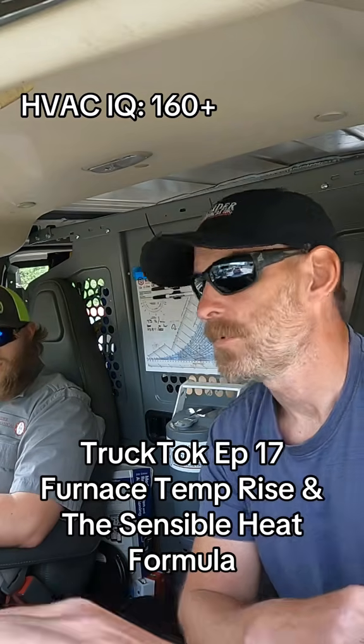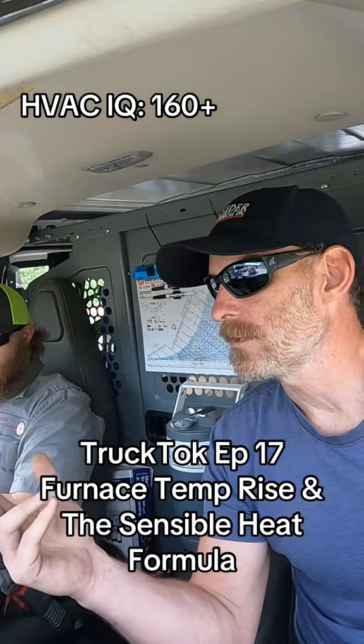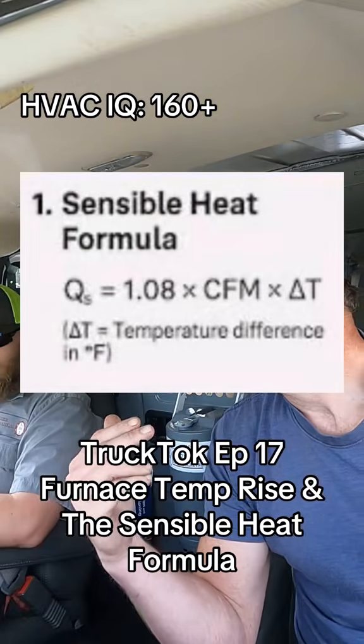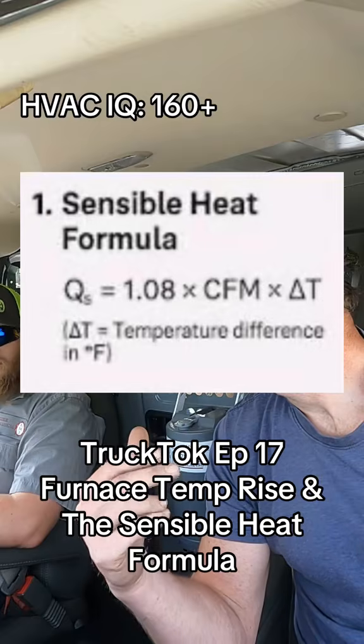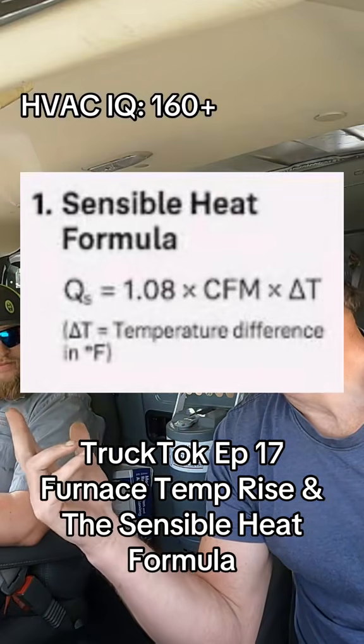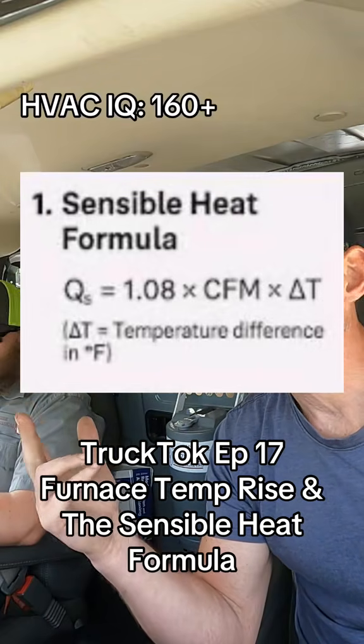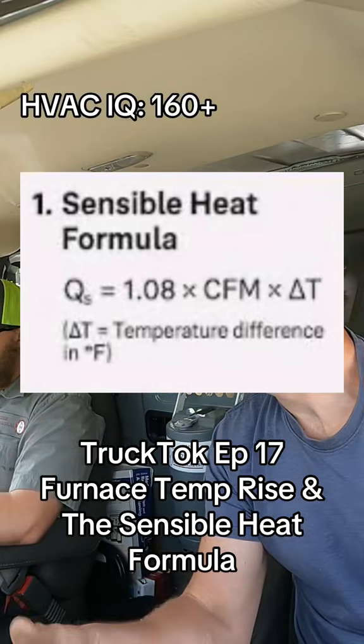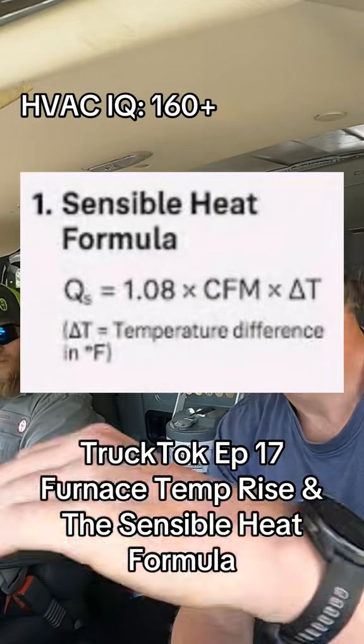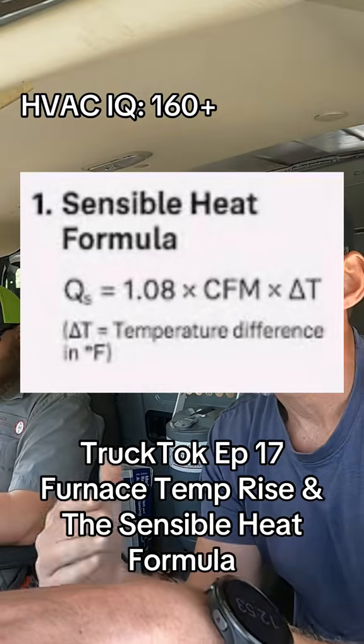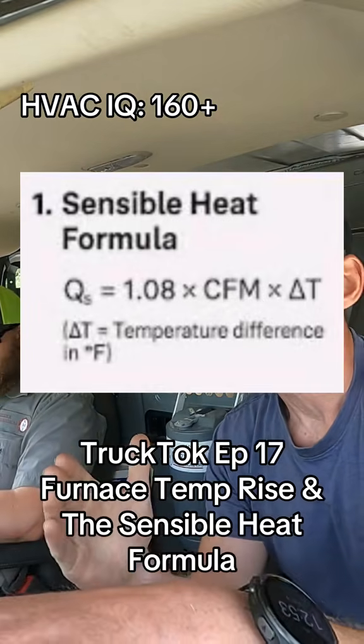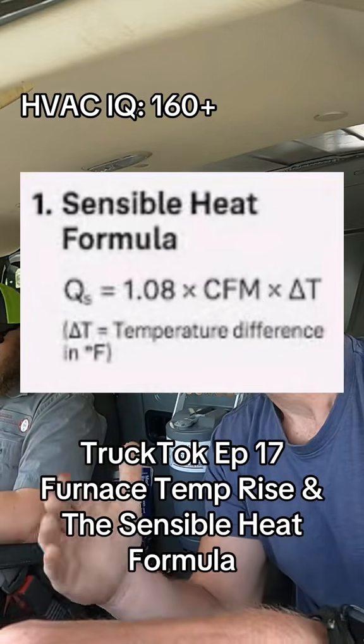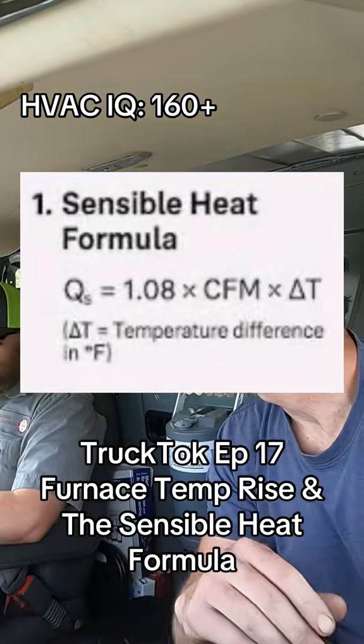But the whole reason that they're able to put that value on there is based on the sensible heat equation. You remember that? There was one for water, remember, for the universal hydronic equation? It had that constant 500 in it. Well, there's one for air too, and it's Q equals 1.08 times CFM times the temperature difference.